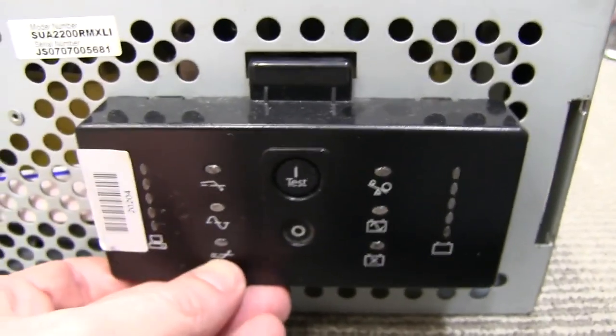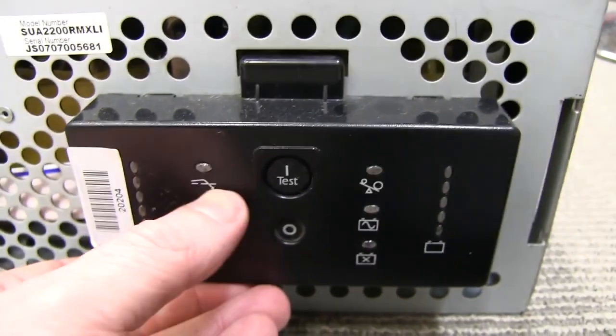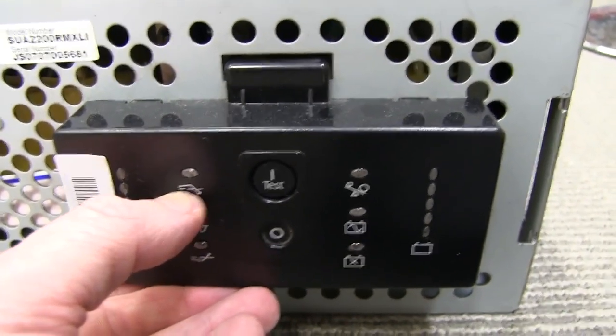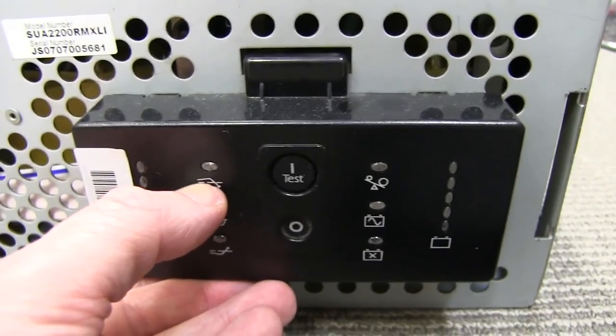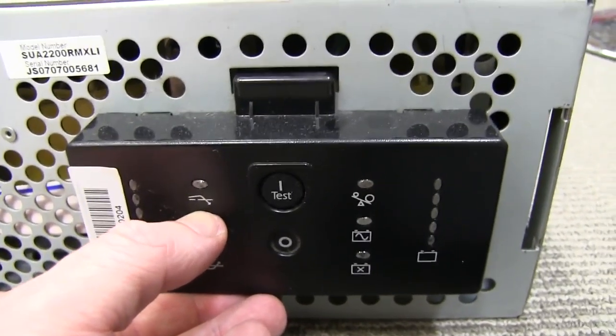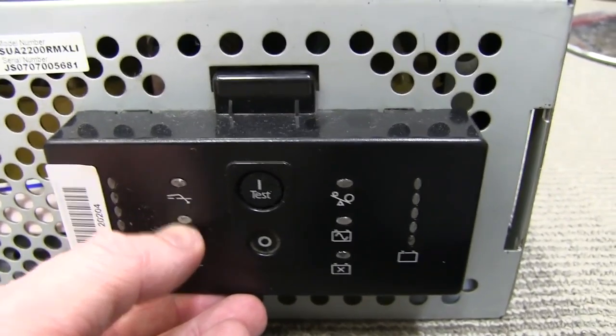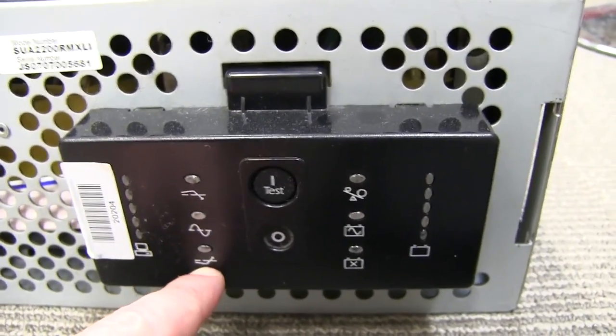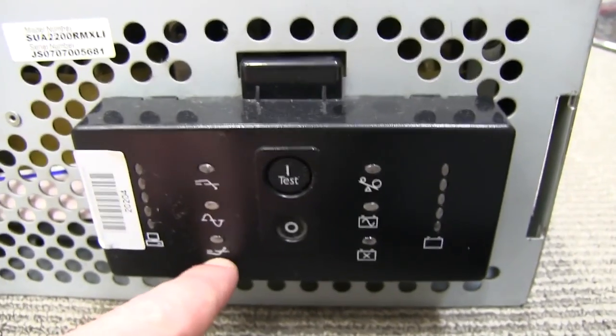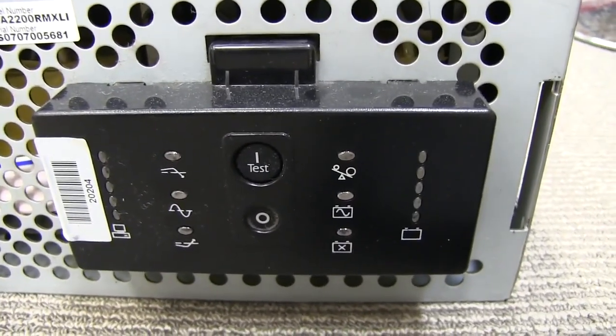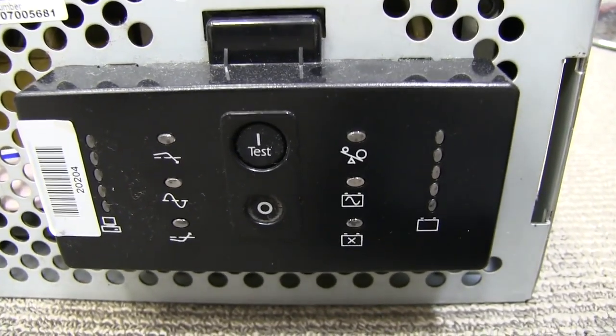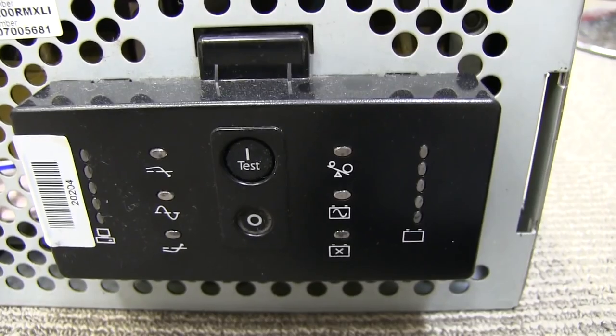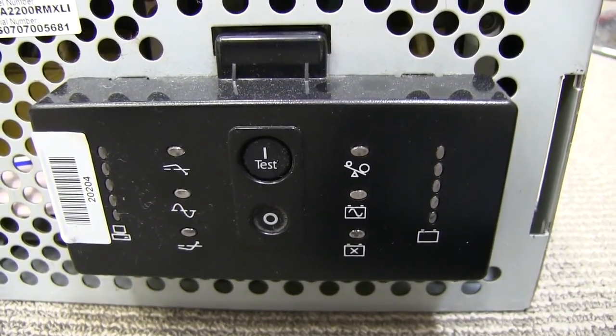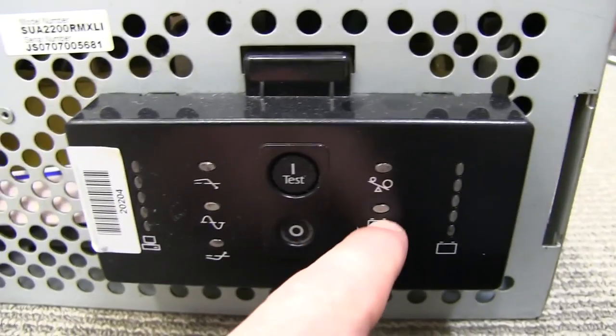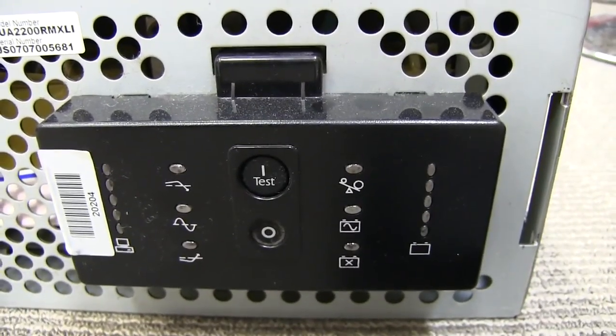And you can see on the control panel here why it's a line interactive UPS. It's got 2 LEDs - one to indicate that the mains voltage has gone over voltage and it needs to correct and pull it back down, so it needs to switch in that extra tap. And likewise, if the mains voltage is sagging, it needs to pull it up and correct it. So obviously it's switching in the taps on the auto transformer, and there's charge level and various other indicators, bad battery, and I think one LED comes on when it's powered from the battery, plus some test functionality.